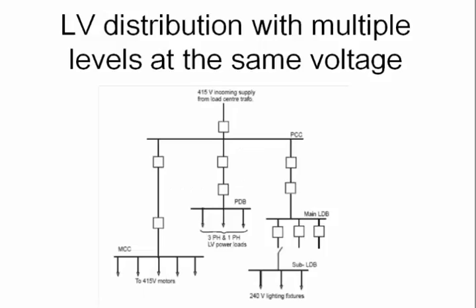So LV distribution with multiple levels at the same voltage, so you have 415. What is MCC? Motor Control Center. You might have smaller motors powered from this panel, power distribution board, 3-phase and 1-phase LV loads, main low voltage distribution board, lighting distribution board for lighting, sub LDB for lighting fixtures. This is your power control center. So this is your low voltage distribution.